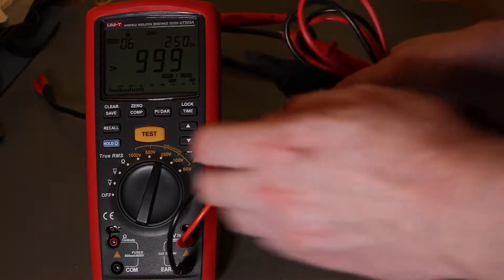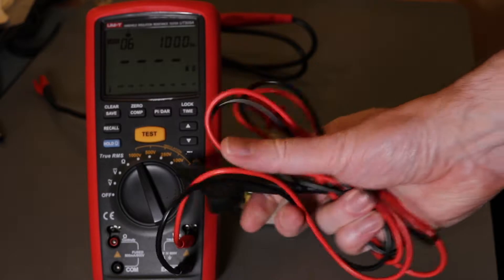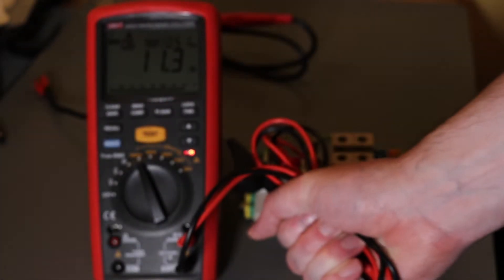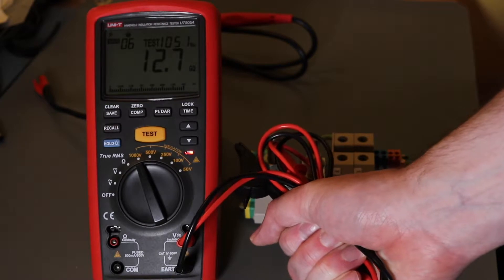OK, so a little demo of the quality of the leads, scrunching up together, take up to 1000 volts. Hit the test button, it goes up to 20 gig ohms max on this range.